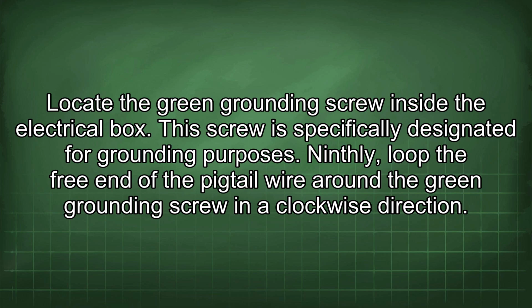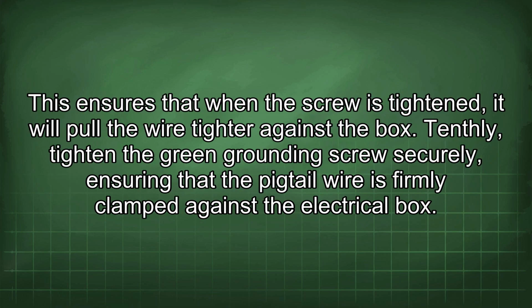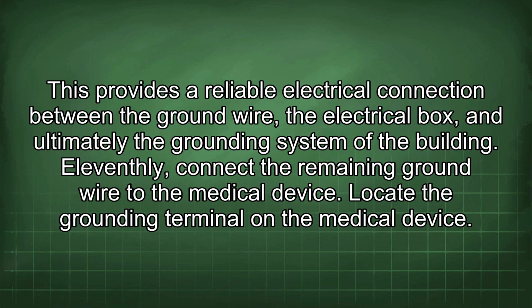Ninthly, loop the free end of the pigtail wire around the green grounding screw in a clockwise direction. This ensures that when the screw is tightened, it will pull the wire tighter against the box. Tenthly, tighten the green grounding screw securely, ensuring that the pigtail wire is firmly clamped against the electrical box. This provides a reliable electrical connection between the ground wire, the electrical box, and ultimately the grounding system of the building. 11thly, connect the remaining ground wire to the medical device.